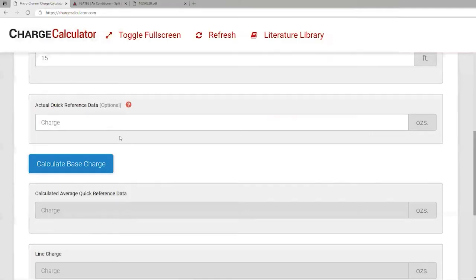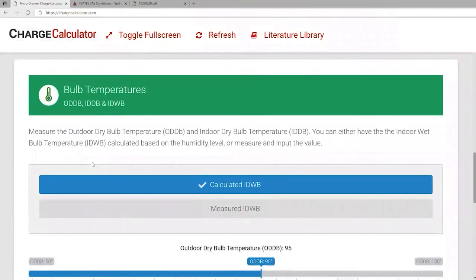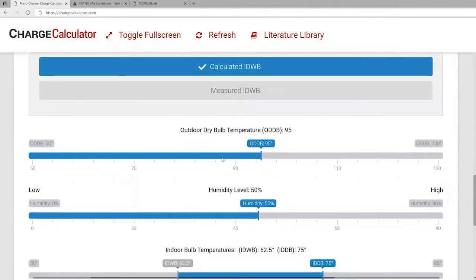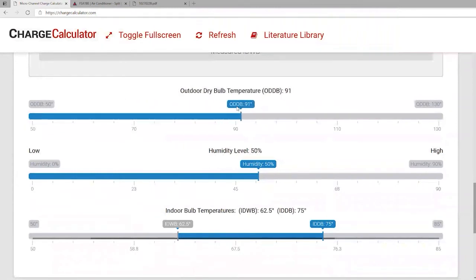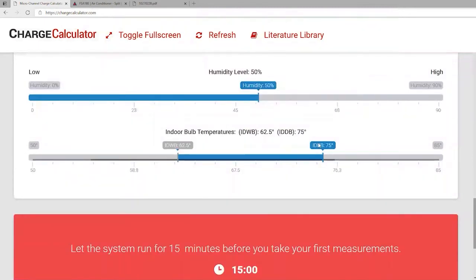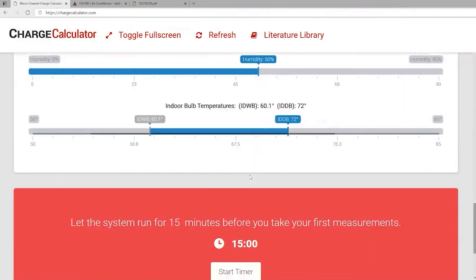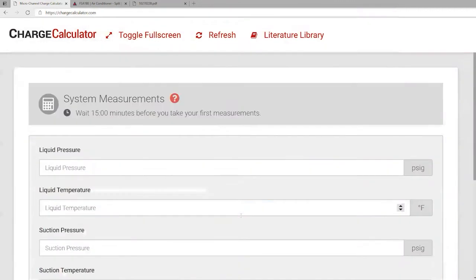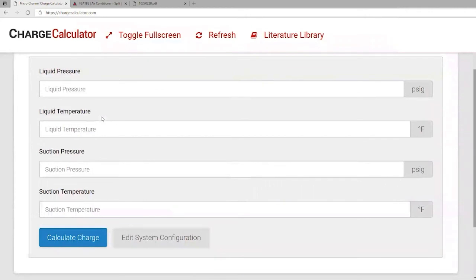Going back to the charge calculator and hitting 'Base Charge,' it prompts the contractor to fill out their outdoor ambient condition, ranging from about 50 to 130 degrees—for our example we'll select 80 degrees. Humidity level, we'll keep at about 50. We'll also need the indoor dry bulb temperature—let's say 72 degrees. The next thing you do is hit 'Start Timer.' The timer shows 15 minutes, but you don't have to wait 15 minutes to check your charge—it's just a good reference point for when you actually started checking your charge amount.